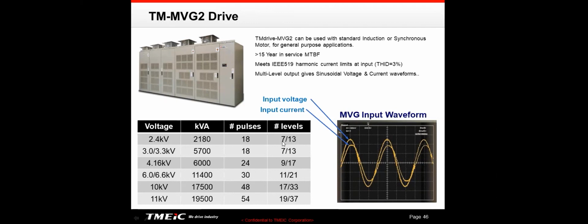So the lowest level we get is a 7 level. That's the output to the motor. And the pulses has to do with the utility. And it's 18 pulse, but only in the 2400 volt version. And then you get to 24 and even as high as 54 pulses.